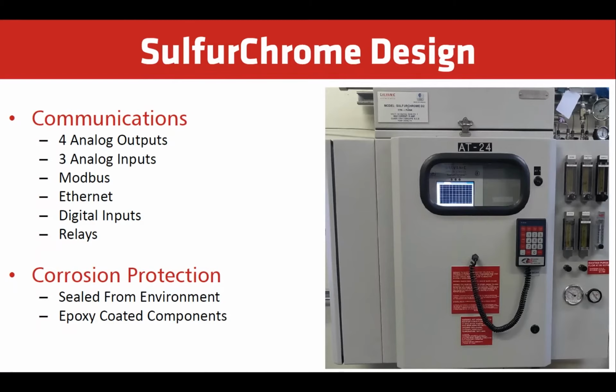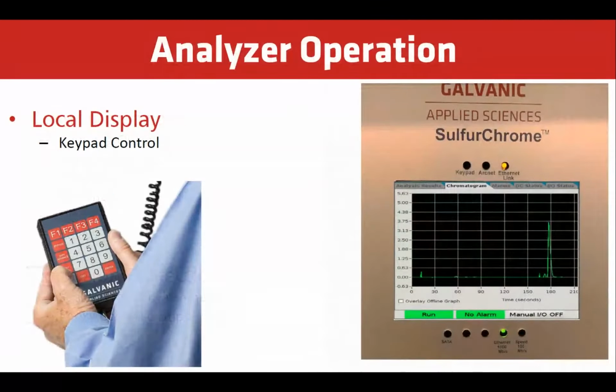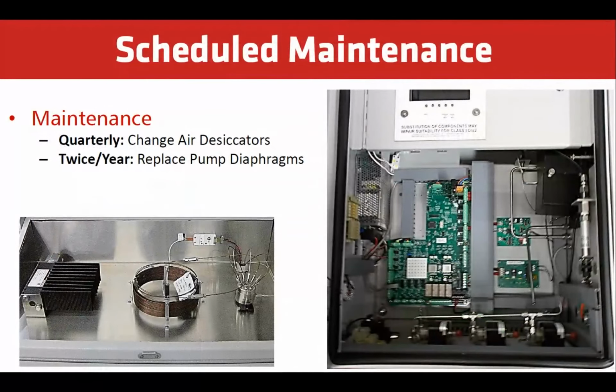Corrosion protection: sealed, with epoxy components. Analyzer operation has a local display and a keypad control, which is intrinsically safe, so it allows the operator to make changes. Scheduled maintenance: quarterly, change the air desiccators; twice a year, replace the pump diaphragms. The desiccators are located on the right-hand side of the analyzer. This is where the ozone air is drawn through, and the combustion air. So we're delivering dry ambient air to those components to prevent any damage to the analyzer.